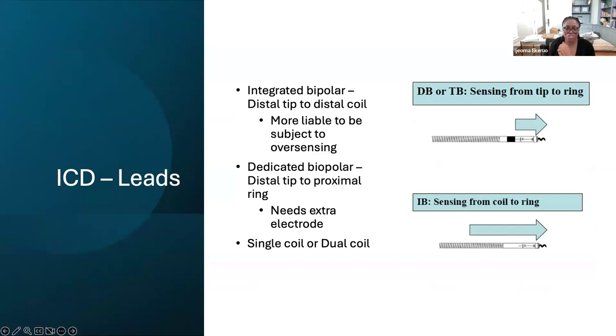The other thing I want to talk to you about is, sometimes you'll hear us talking about integrated bipolar versus dedicated bipolar. A dedicated bipolar looks more like this, where you have an electrode at the tip, and then you have your cathode going to your anode. It's able to sense from your tip to a ring, versus the integrated bipolar, which basically senses from the tip to the distal coil, and gives you a larger antenna. So it can be a good thing in that the engineering doesn't have an extra place for oversensing or breakage, but the disadvantage is that it's more liable to have oversensing because you have a larger antenna.